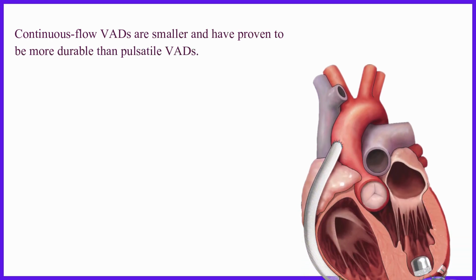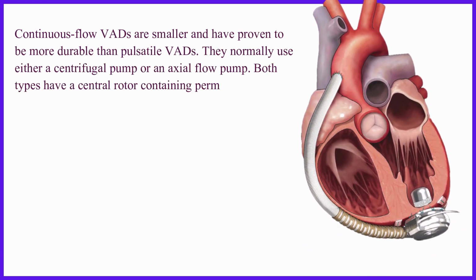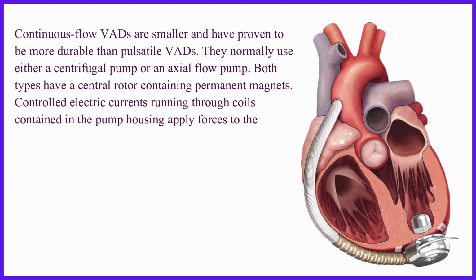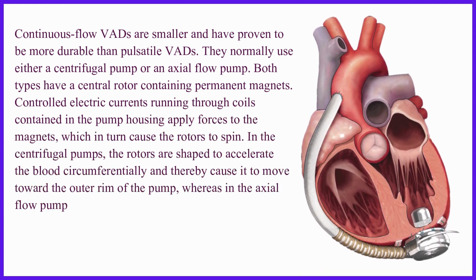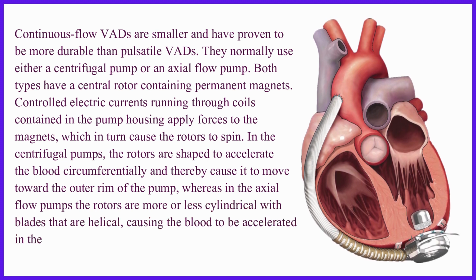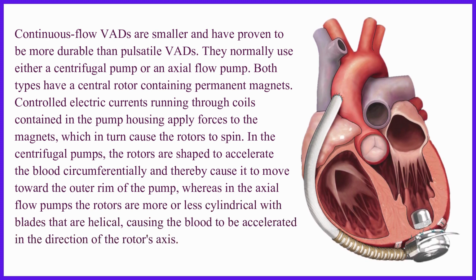Continuous flow VADs are smaller and have proven to be more durable than pulsatile VADs. They normally use either a centrifugal pump or an axial flow pump. Both types have a central rotor containing permanent magnets.